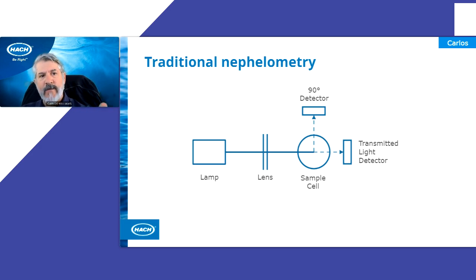So here again, this is one design of a traditional nephelometer. You've got a lamp, a lens, and a sample cell. If you're using an online measurement, you won't necessarily have a sample cell, and you may have other detectors. So you may have one at 90 degrees, you may have one at 180 degrees or at 45 degrees. And then in some cases, you'll have a transmitted light detector as well, because if we can, it'd be nice to account for transmitted light. When we have a sample that has not only turbidity but color in it, the color will absorb some of the wavelengths of light. So if we can compensate for that using a transmitted light detector, that's what we like to do. The transmitted light detector is typically something that we find on lab instruments and not on process instruments, but it's a handy tool to have.